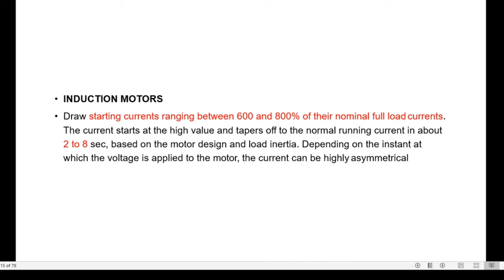See what a huge amount of current will be drawn from the supply for the starting of a heavy induction motor. The current starts at a high value and then tapers off to the normal running current in about 2 to 8 seconds. But that is also enough time to create the voltage sag, based on the motor design and load inertia. Depending on the instant at which the voltage is applied to the motor, the current can be highly asymmetrical. Please keep in mind, the current will be highly unsymmetrical.